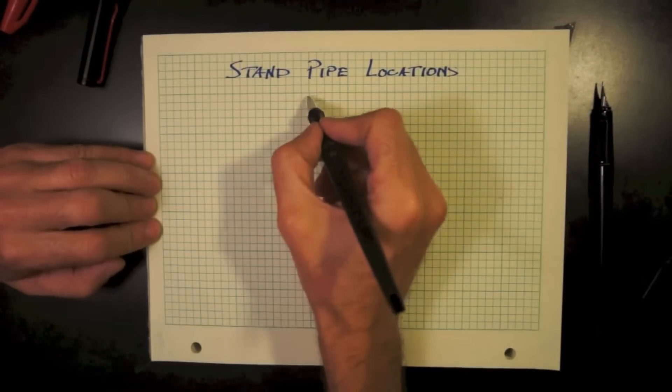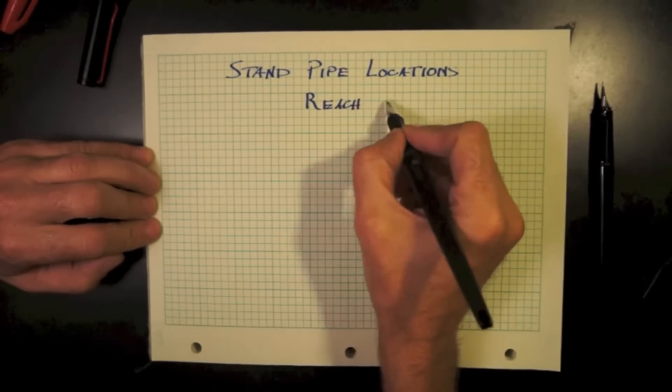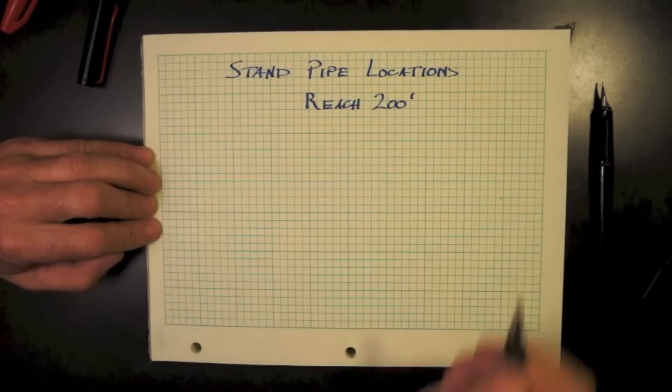Standpipe location. Reach distance is 200 feet. You must be able to access a standpipe within 200 feet.